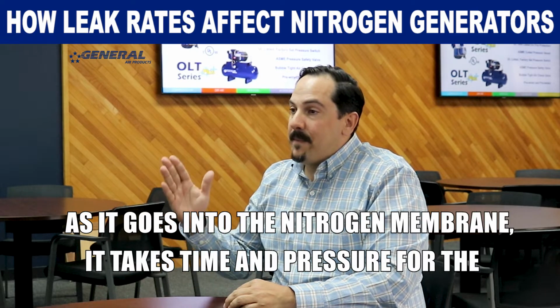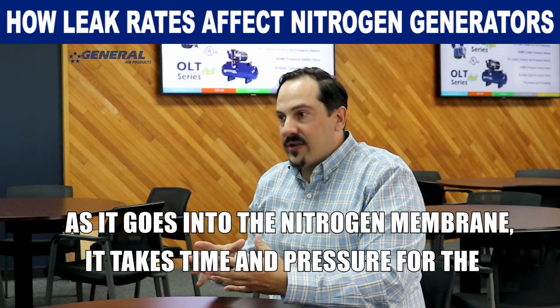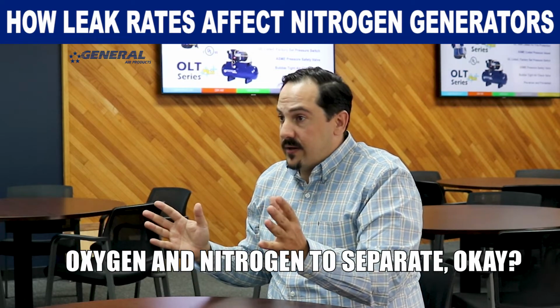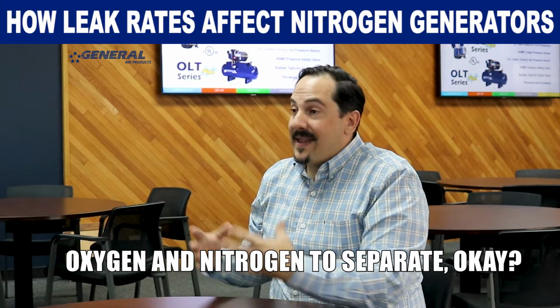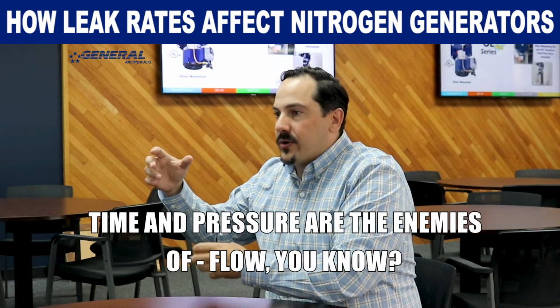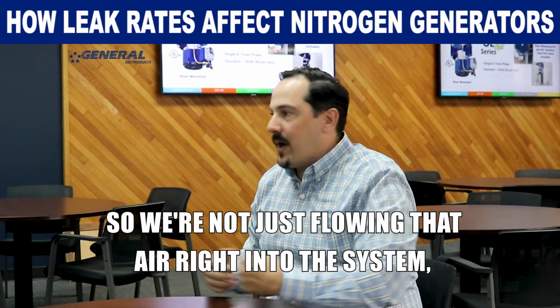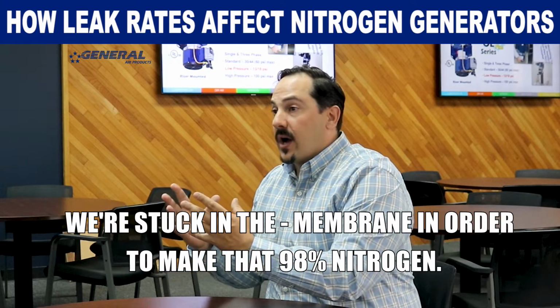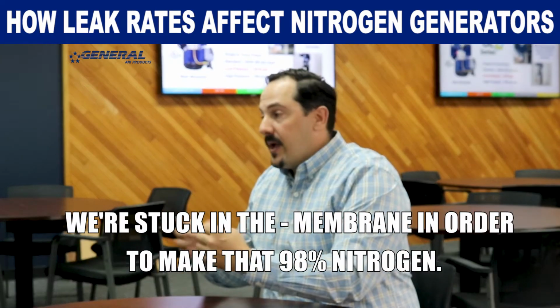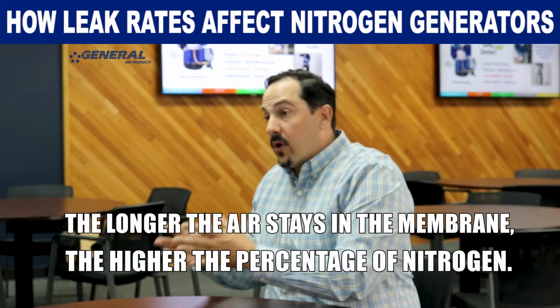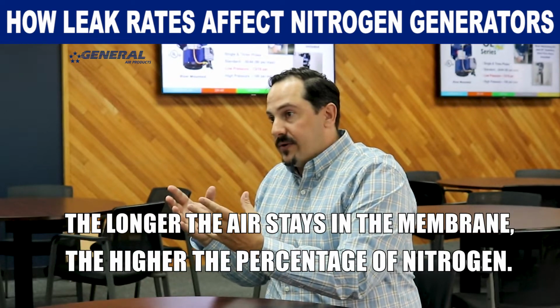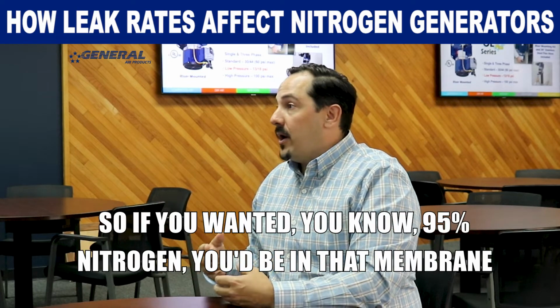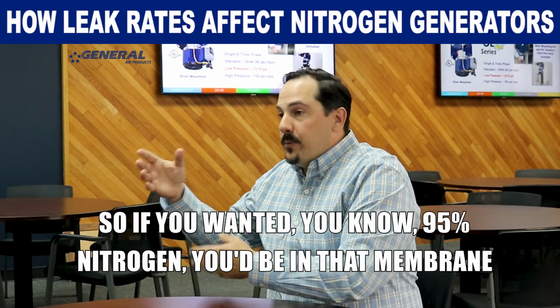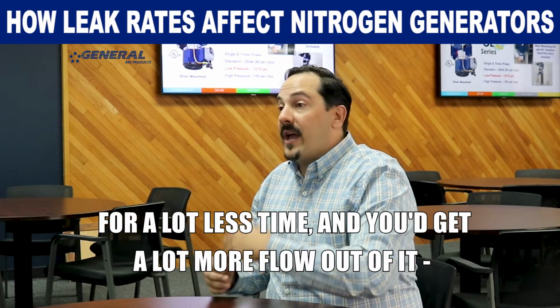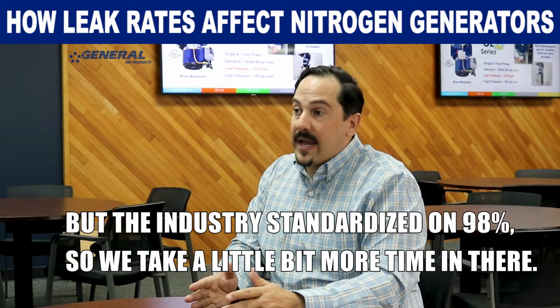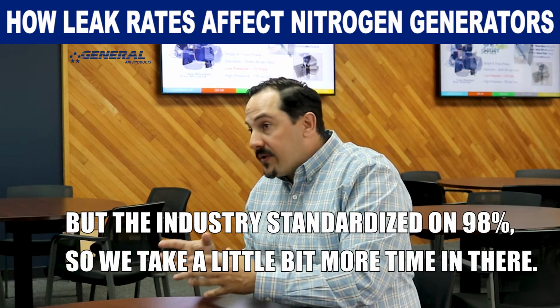As it goes into the nitrogen membrane, it takes time and pressure for the oxygen and nitrogen to separate, and time and pressure are the enemies of flow, so we're not just flowing that air right into the system. We're stuck in the membrane in order to make that 98% nitrogen. The longer the air stays in the membrane, the higher the percentage of nitrogen. If you wanted 95% nitrogen, you'd be in the membrane for a lot less time and get a lot more flow out of it. But the industry standardized on 98%, so we take a little bit more time in there.